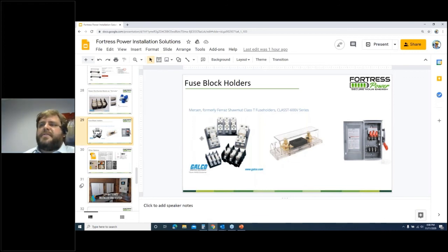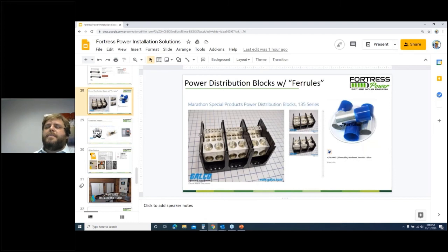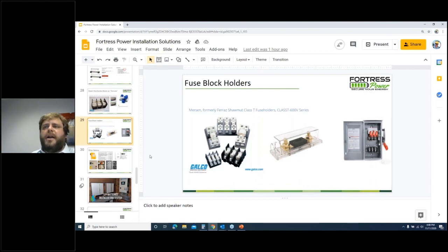Yeah, and so in this other slide, we're showing, if you combine a power distribution block, the one thing that it doesn't have is overcurrent protection. Terminal blocks for overcurrent protection, fuse holders, fuse blocks are a little bit easier to come by. Heck, a knife switch disconnect will often have a fused option for holding fuses. Now, our batteries, inside their battery management system, do have fuses for overcurrent protection or inrush current, to make sure that if whatever the installer does gets back to the battery, the component that fails will be part of our battery management system and not the battery itself.